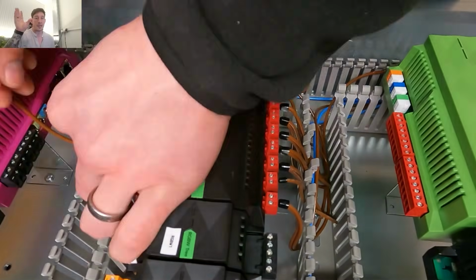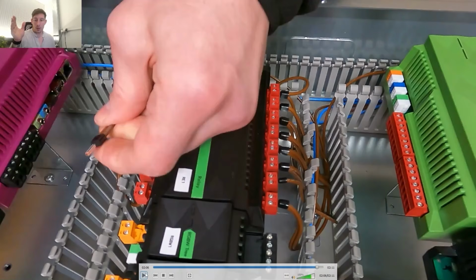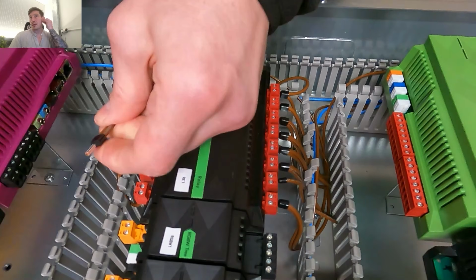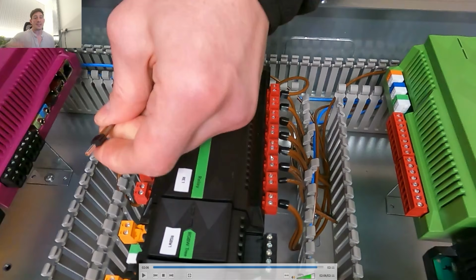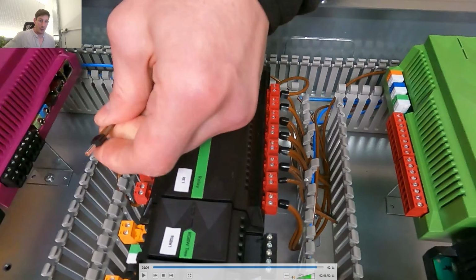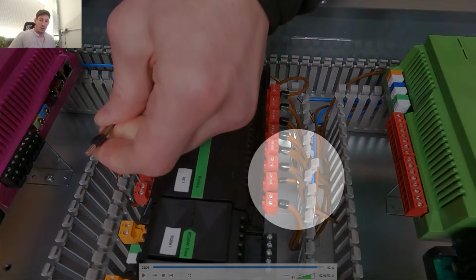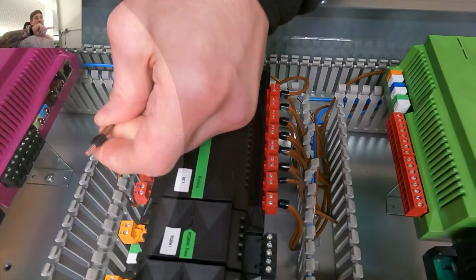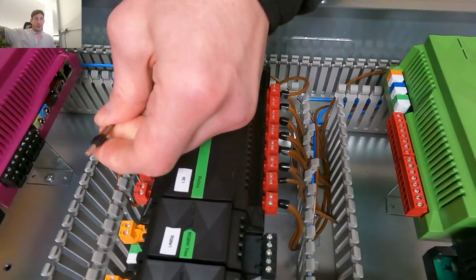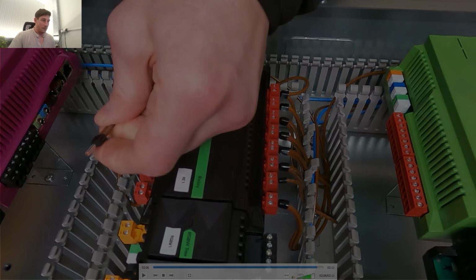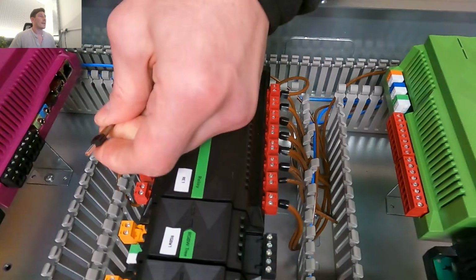It will just switch automatically on or off. For example, with lighting outside, we could have it on a time schedule, or when it gets to dusk, then switch on the outside light. So it will go from that constant 24 volt feed, switch that relay, and send the power out on this cable, down to the terminal block, through the cables out in the field, off to the light, and then back on the neutral to that terminal block, and the neutral goes back to that RCBO. Hopefully that makes sense.